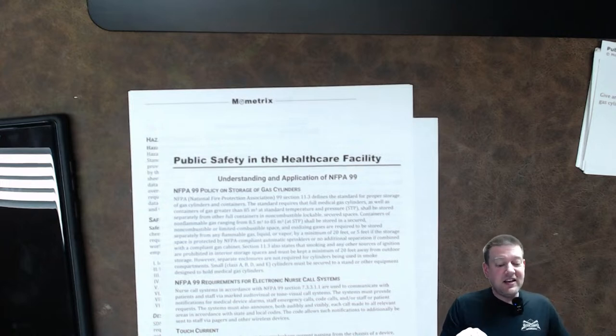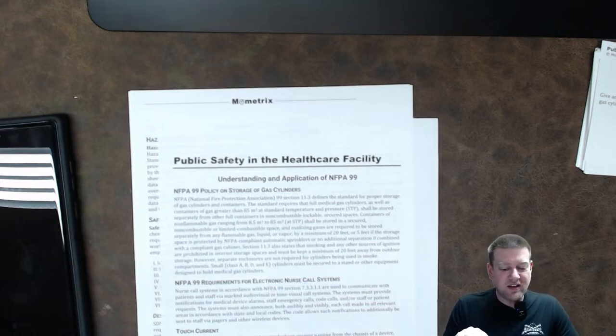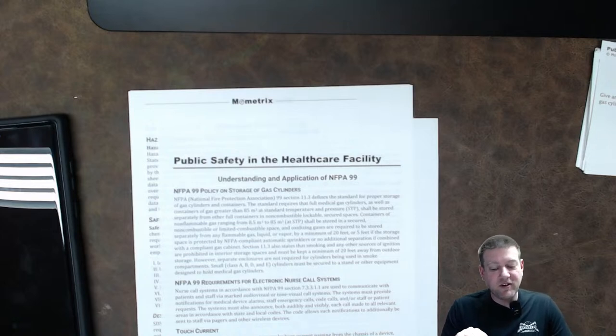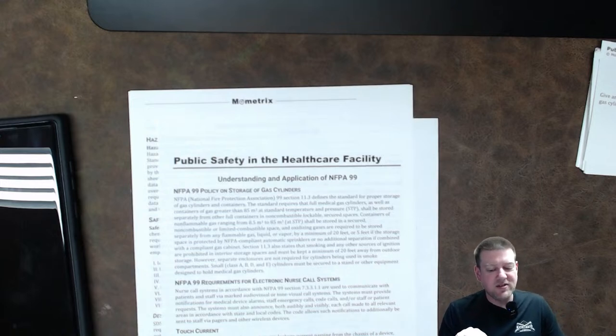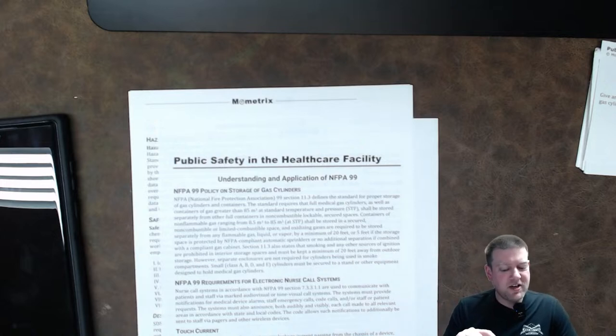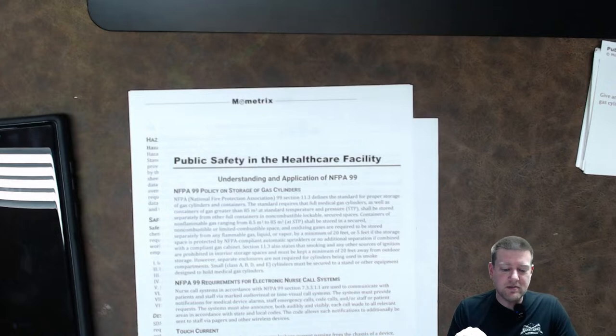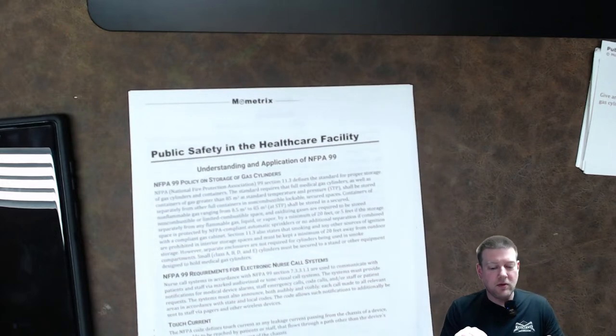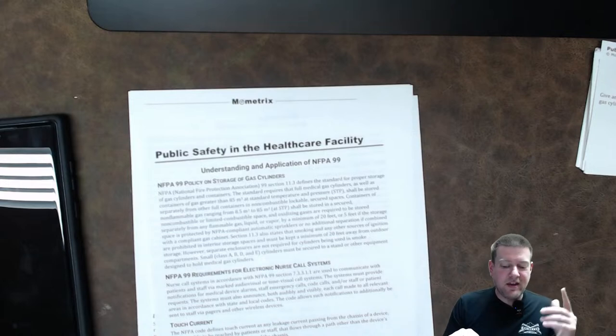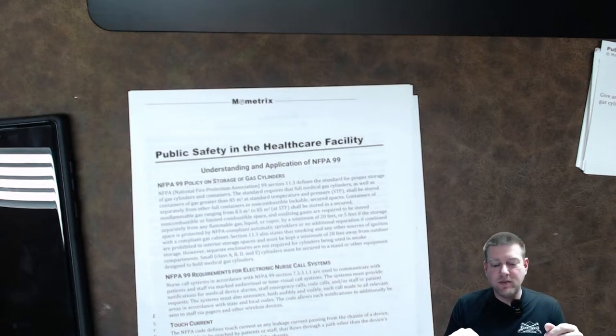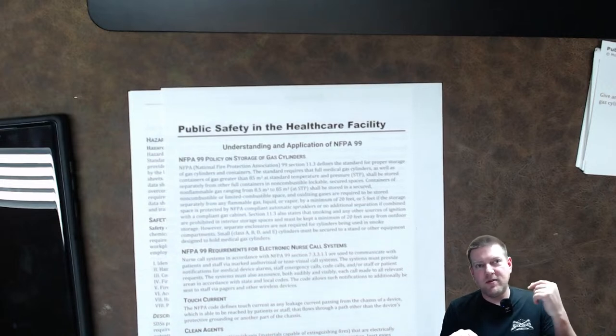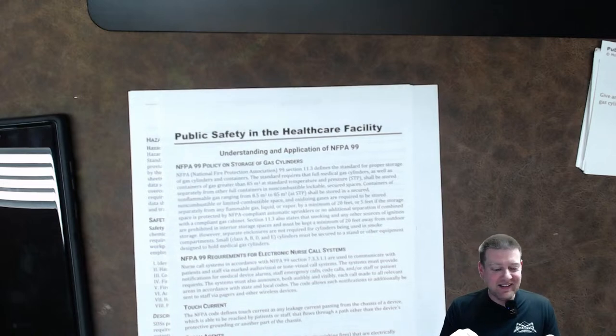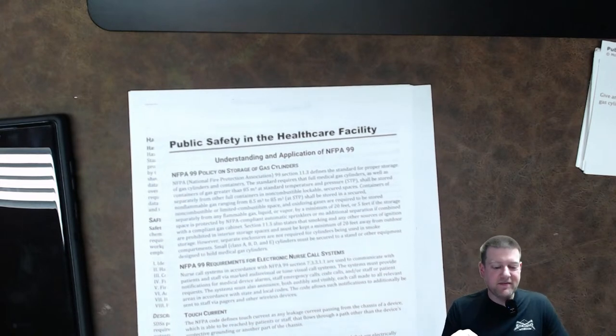Clean agents. Clean agents are extinguishants, materials capable of extinguishing fires, that are electrically non-conductive, volatile, or gaseous, and do not leave residues upon evaporation. Inert gases, nitrogen, carbon dioxide, and noble gases are clean agents. Okay? So inert gases. And the key is it can't leave a residue. So a lot of your sodium bicarbonate fire extinguishers, they leave a residue, and it's nasty. All right? Very cool.